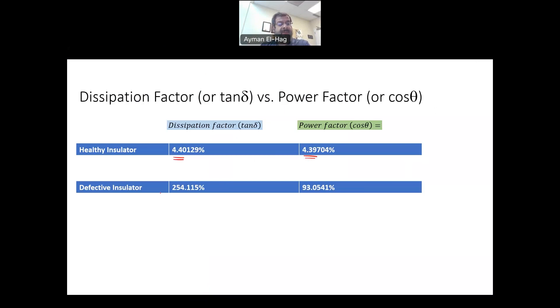However, for the defective insulator, the dissipation factor was 254% — much higher. This has been covered in the previous video. But the power factor is 93%. So why is there this discrepancy?